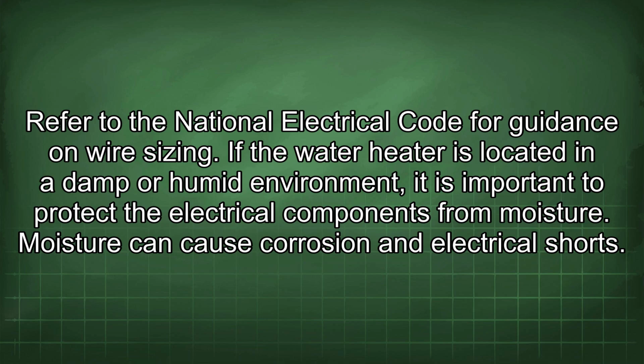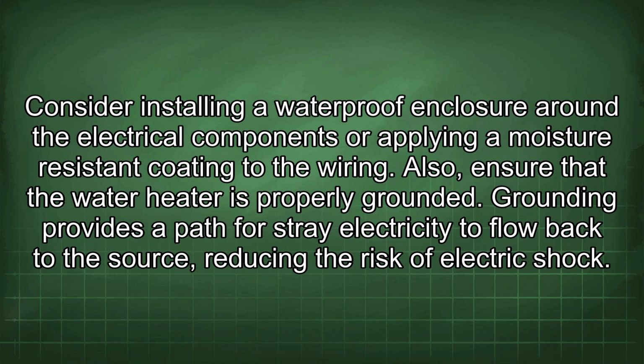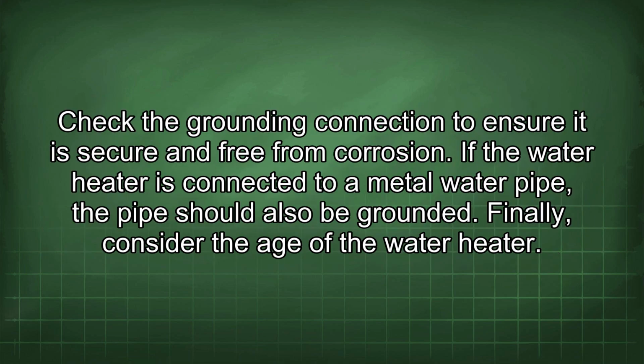If the water heater is located in a damp or humid environment, it is important to protect the electrical components from moisture. Moisture can cause corrosion and electrical shorts. Consider installing a waterproof enclosure around the electrical components or applying a moisture-resistant coating to the wiring. Also, ensure that the water heater is properly grounded. Grounding provides a path for stray electricity to flow back to the source, reducing the risk of electric shock. Check the grounding connection to ensure it is secure and free from corrosion. If the water heater is connected to a metal water pipe, the pipe should also be grounded.